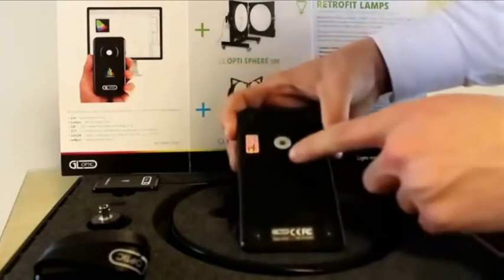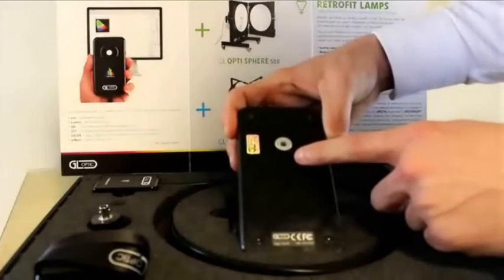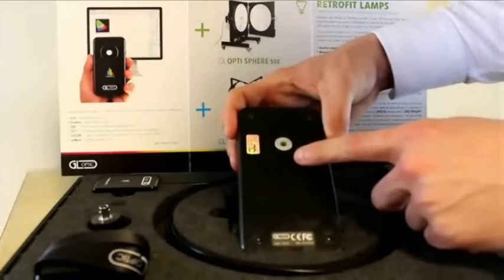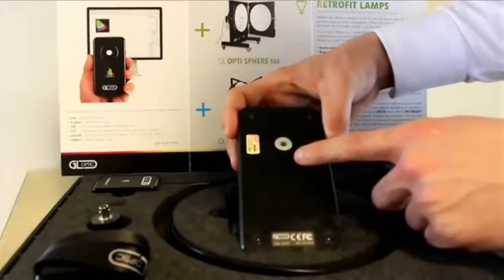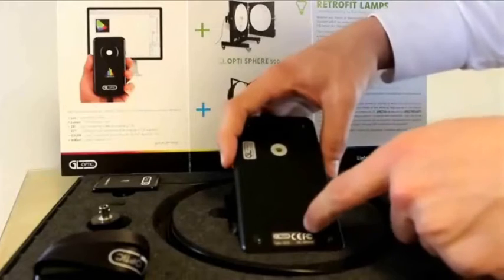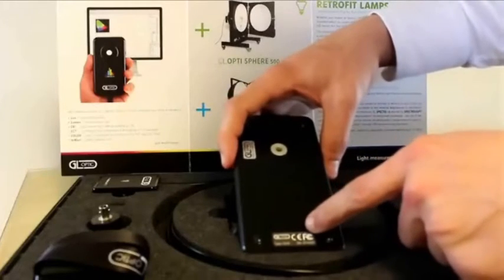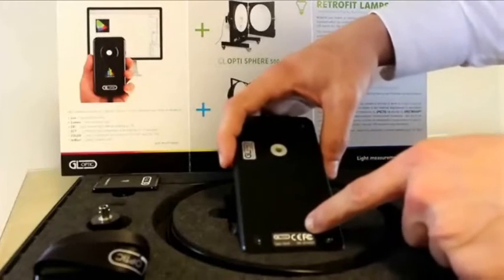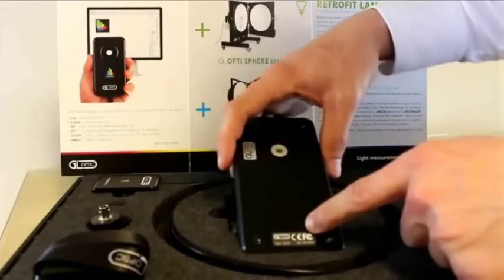Behind the back casing here, you would find the sensor, which runs from 340 to 715 nanometres, and also the lithium-ion battery, which gives the user six hours of continuous measurement.